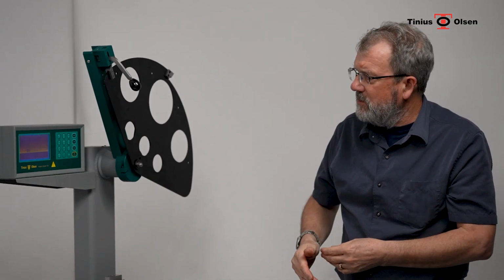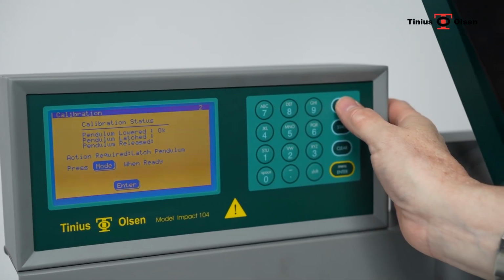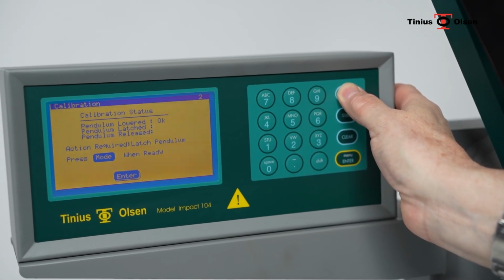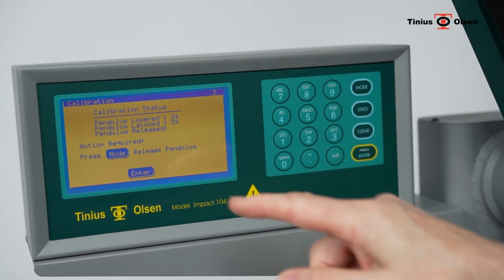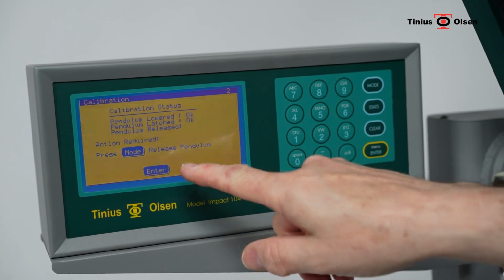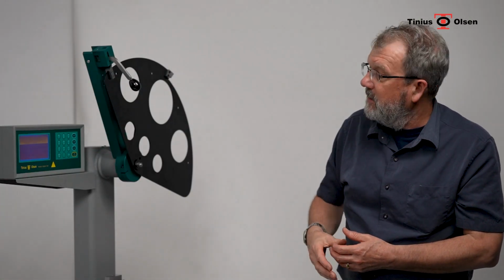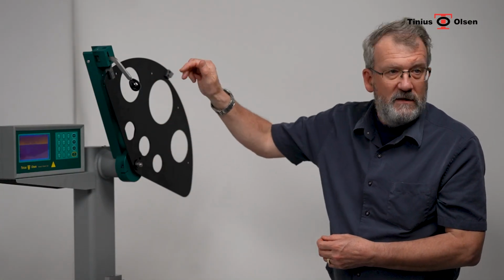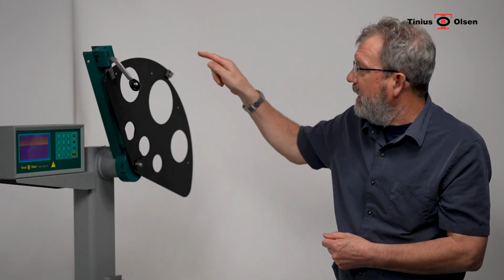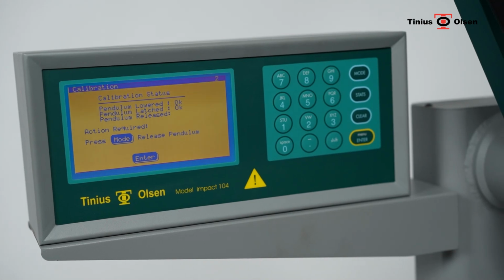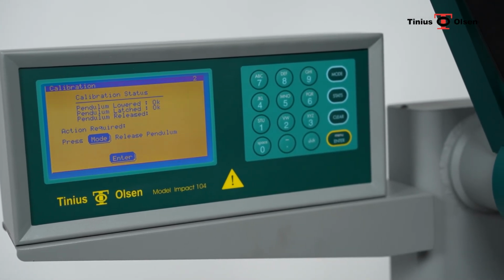Once it is in that position, we can press the mode button, and what happens now is the encoder has counted the position of the pendulum and knows exactly the angle that that pendulum is at. Because the system already knows the length of the pendulum, it can calculate the height that this striker is above the sample. The screen now says action required, press mode, release pendulum.